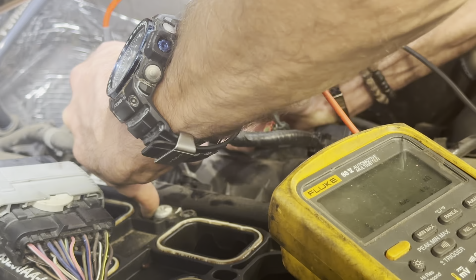20, 28, 29, it's sitting there changing because it's trying to send something through those windings, and then it went open here. So that is, if I can see, that's thousands of ohms. That's kilo ohms. So that is 39,000, 49,000, 42,000. That is basically 40,000 ohms. It's open. I mean, the coils are no good in it.